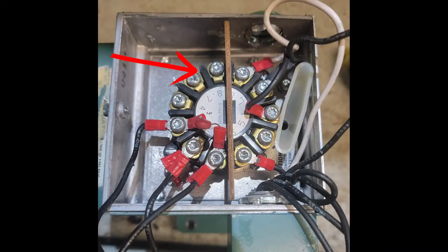This is what happens when your library is a little bit too much of a mess. Here we go. Okay, so this is what that actuator wiring looks like. So yeah, this can get a little complicated. So I'd say this is one thing to really pay attention to. Make sure everything is wired and labeled appropriately, and you're really identifying what goes where. Also, another thing to verify is that, depending on how old the machine was that you're replacing the actuator on, make sure that the wiring to the new one is exactly the same as the old one, and that things didn't slightly get moved or pivoted around.